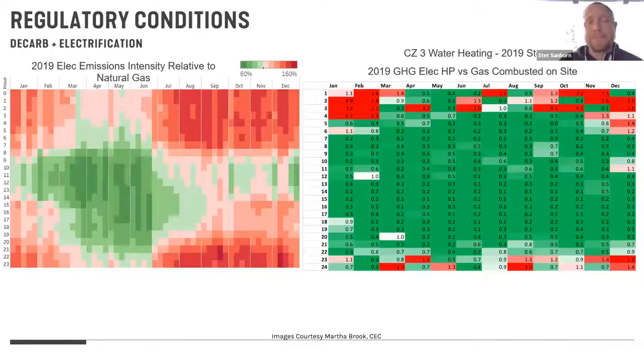What we do on our projects is start to look at the hourly use of energy. From the graph on the left, from midnight to midnight, and January all the way through December, what hours are we using energy and what's the carbon emissions for that hour? We call that our marginal emissions rate, the additional carbon associated with using power for that hour. The image on the left compares using electric resistance for, say, domestic hot water production or space heating to burning natural gas on site. And that's with all the losses through the grid: generation losses, distribution losses, transformer losses, et cetera.